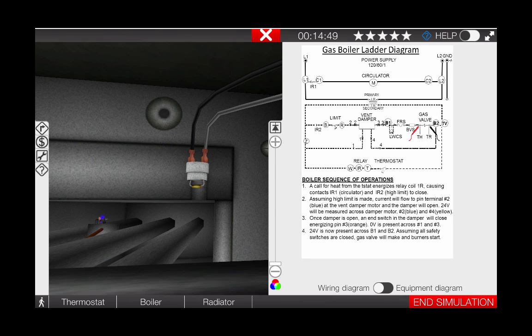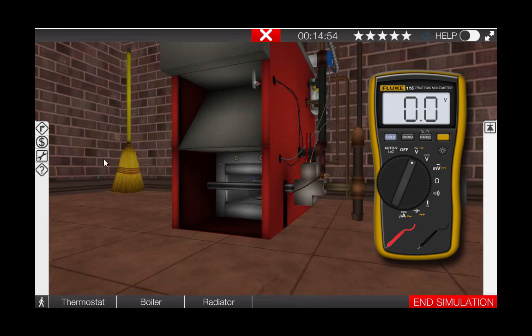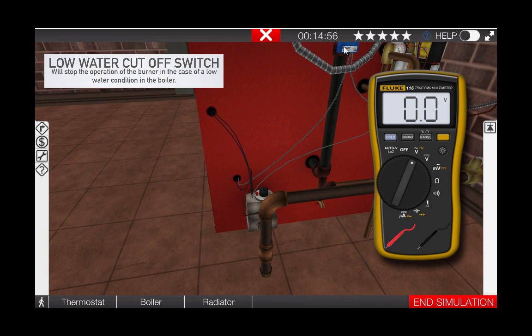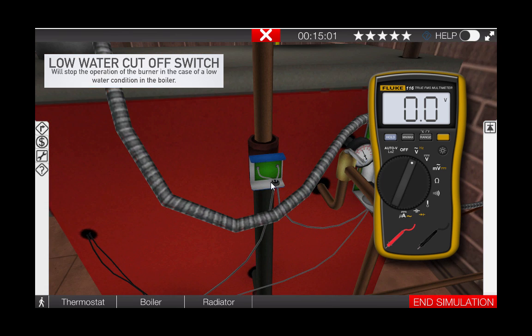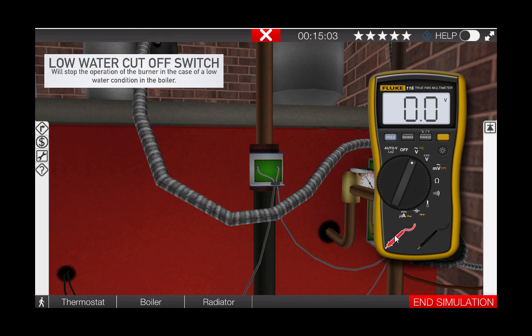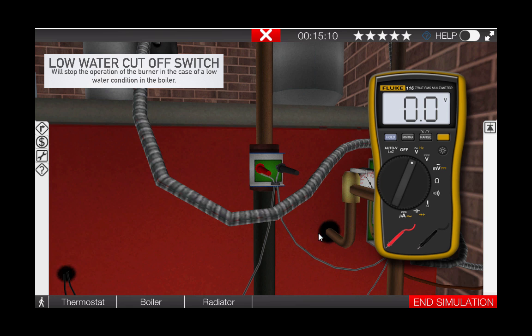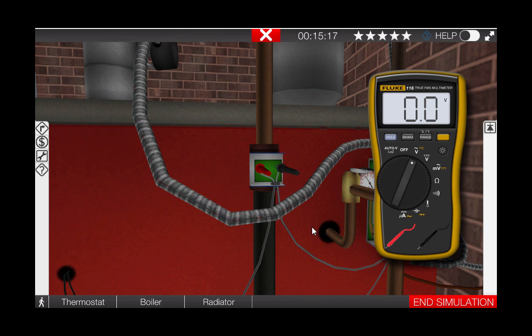We're going to check each one of these switches. First, let's go back to the low water cutoff. Zoom out, locate the low water cutoff, and remove its cover. Center it in your field of view by clicking on it. Click on the meter leads and place them at the glowing hotspots on the low water cutoff. We can see that we have zero volts across the low water cutoff. This indicates no difference in electrical potential across the switch and verifies that the switch is in fact in the closed position.